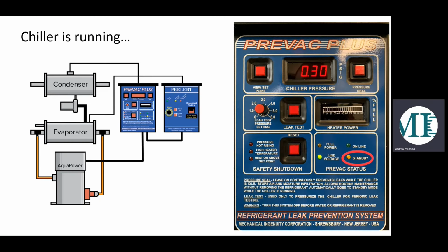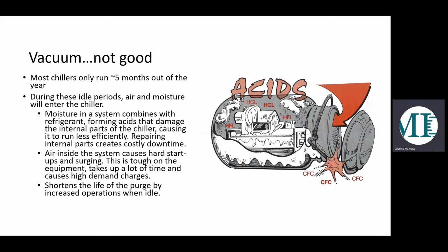When the chiller's running, it's business as usual. The PREVAC is in standby mode. So when the chiller shuts down, that's when low pressure chillers do go into a vacuum, which is going to be a problem because it absorbs moisture and air from the atmosphere. That moisture is going to combine with the refrigerant. It's going to cause buildup and acid inside the tubes and is just overall harmful to the equipment. The air inside the system is going to cause hard startups and surging.